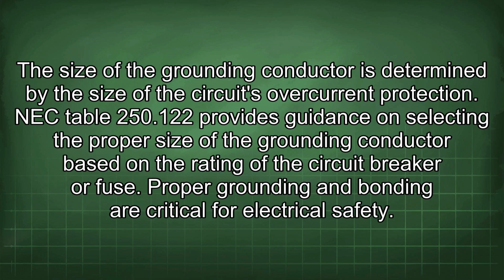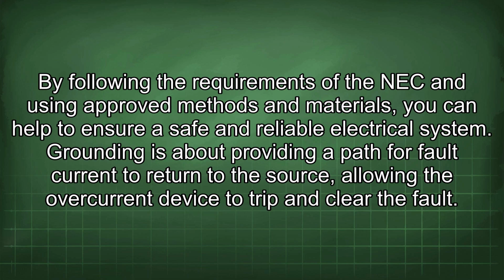250.122 provides guidance on selecting the proper size of the grounding conductor based on the rating of the circuit breaker or fuse. Proper grounding and bonding are critical for electrical safety. By following the requirements of the NEC and using approved methods and materials, you can help to ensure a safe and reliable electrical system. Grounding is about providing a path for fault current to return to the source, allowing the overcurrent device to trip and clear the fault.